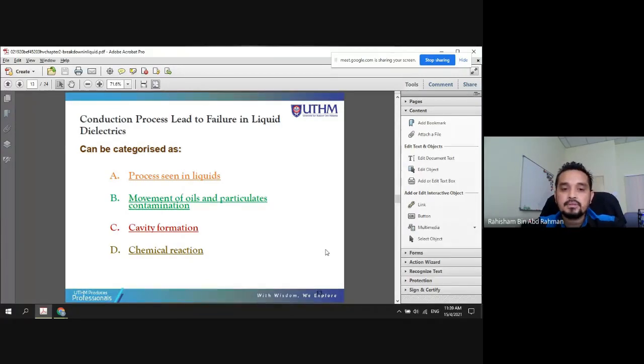The principle is that some of the failure within the liquid is also triggered by the ionization of the material. It's similar to the gas, but it's ionization within the liquid, meaning an atom will have an electron that escapes from its stable condition, and this electron will collide with another electron and with another proton, which will somehow trigger the formation of the conduction process within the dielectric.